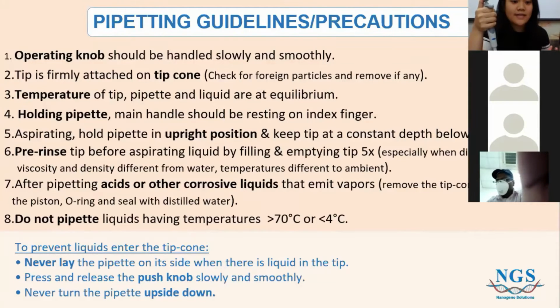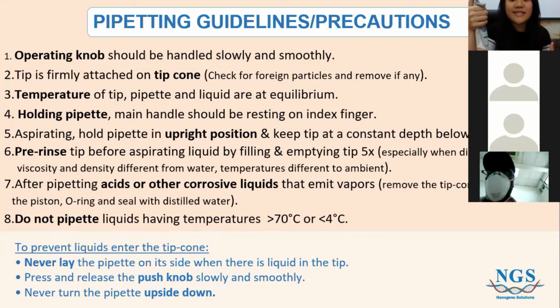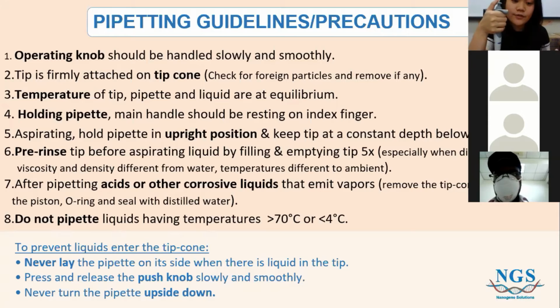After pipetting acid or other corrosive liquid that emits vapor, you should always clean your pipette. Make sure that your pipette is always in good condition by rinsing your tip cone, your piston, and your O-ring with distilled water. And of course, do not pipette liquid at more than 70 degrees Celsius or less than 4 degrees Celsius. This is to ensure that your piston and your tip cone are always in good condition.